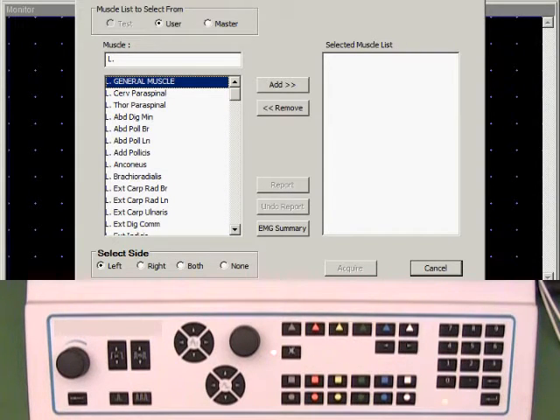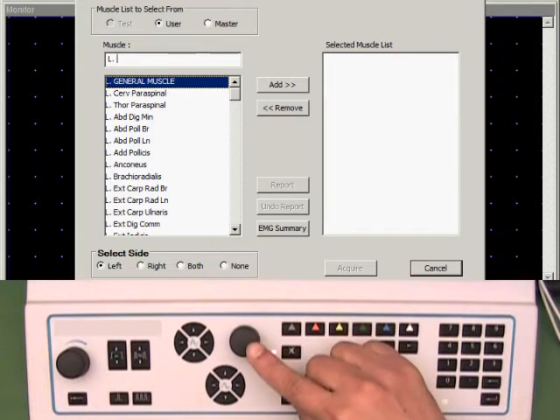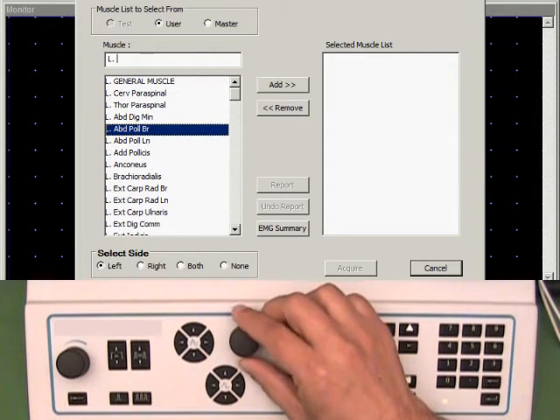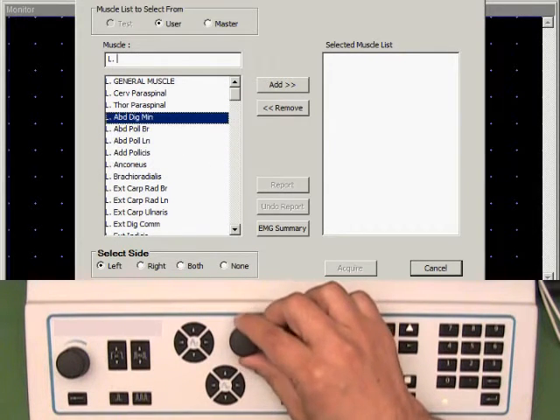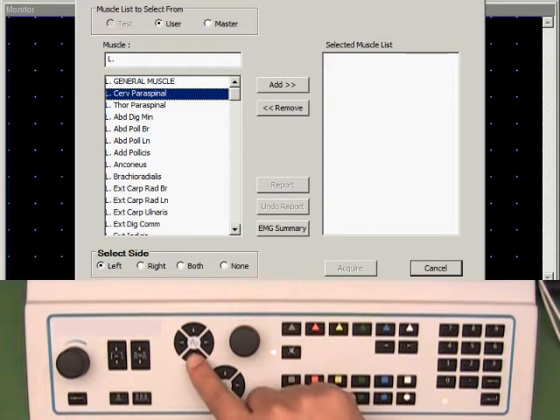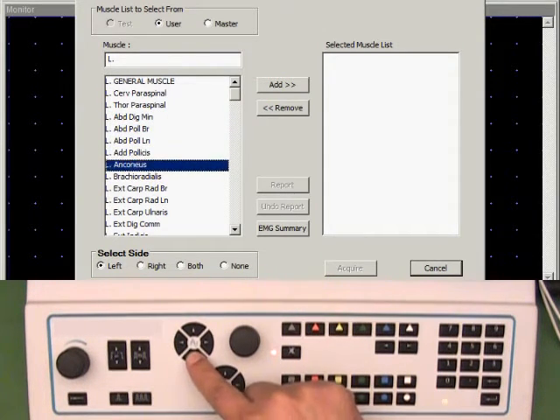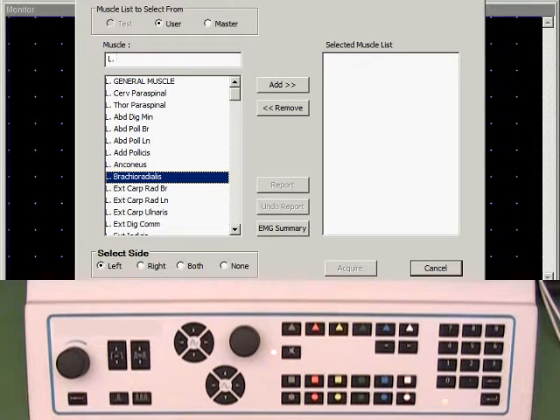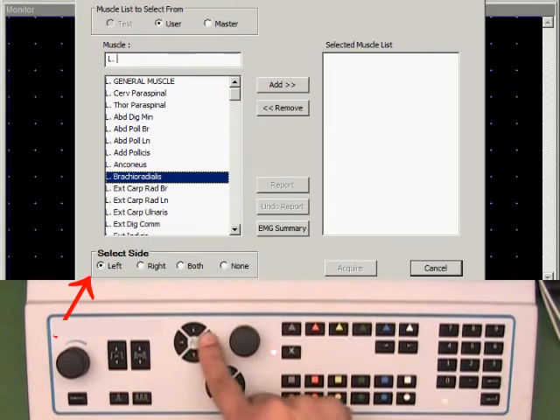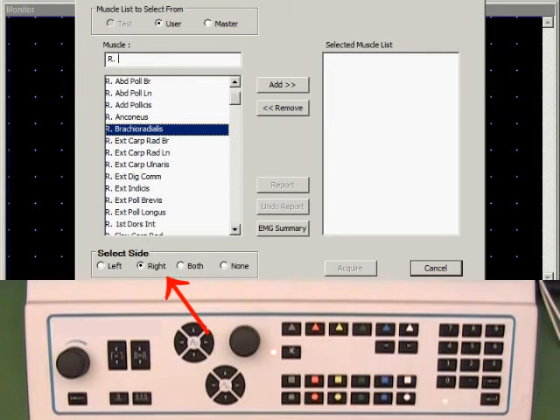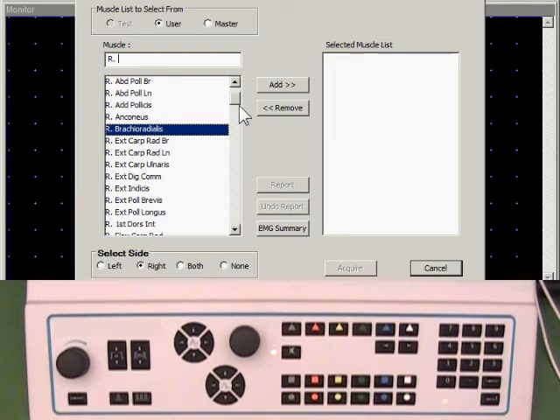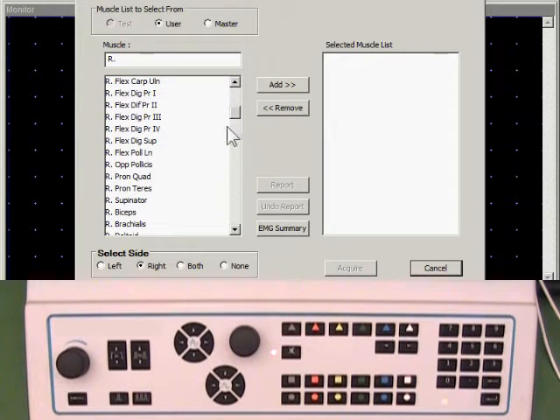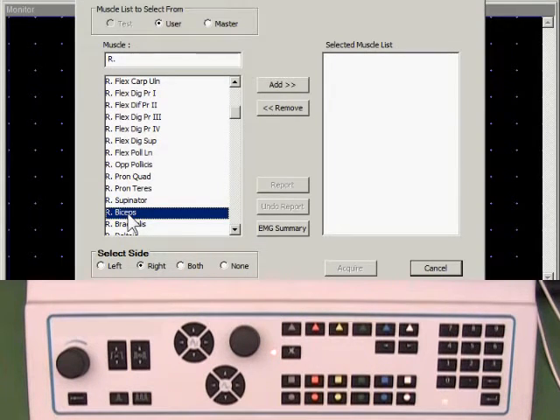A list of muscles is displayed. The general muscle is at the top. One can select the tested muscles in many different ways. We can use the select knob to highlight the desired muscle. We can use the up and down arrow keys to select the desired muscle. We can select the tested side by using the left or right arrow keys. We can also use the mouse to select the muscle. In this case I'm going to test the biceps muscle. I will double click on it.